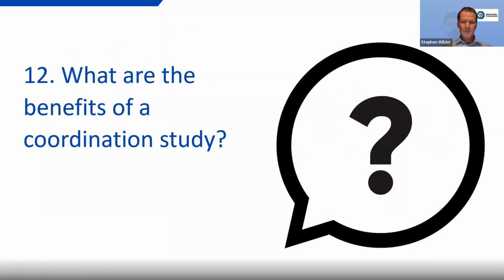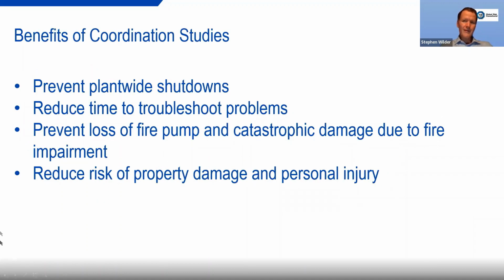Absolutely. So what are the benefits of doing such a study? Well, in large industrial facilities, breaker tripping is very common. Without a coordination study, a short circuit on a small branch breaker could take down the whole plant, or at least significant portions of it, or critical equipment. And it would take a lot of time to troubleshoot where the problem was.